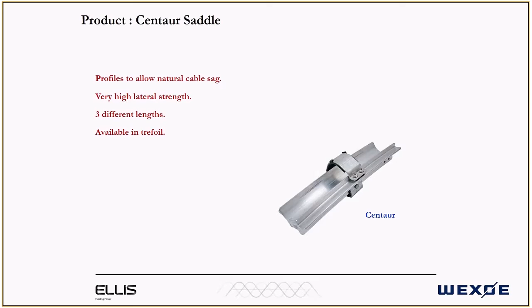This is a specific product used on the utility side, for power tunnels. This is the sagged design, allowing natural cable sag, usually at fixing points 7 or 8 meters apart. It has very high lateral strength, available in 3 different lengths. This shows a single cable version, but it's also available as a trefoil. For large power tunnels or power distribution requirements, it's a versatile product used extensively by National Grid and transmission operators overseas. Simple 2-hole fixings, UV stabilized polymer option, and a marine grade corrosion resistant aluminium option. Single cable formation is a very popular product.